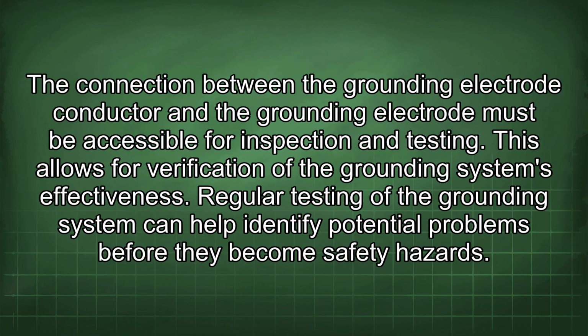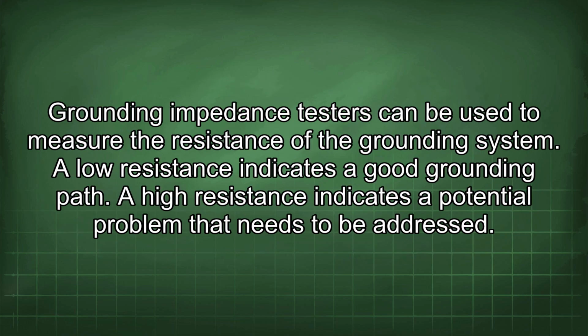The connection between the grounding electrode conductor and the grounding electrode must be accessible for inspection and testing. This allows for verification of the grounding system's effectiveness. Regular testing of the grounding system can help identify potential problems before they become safety hazards. Grounding impedance testers can be used to measure the resistance of the grounding system. A low resistance indicates a good grounding path. A high resistance indicates a potential problem that needs to be addressed.